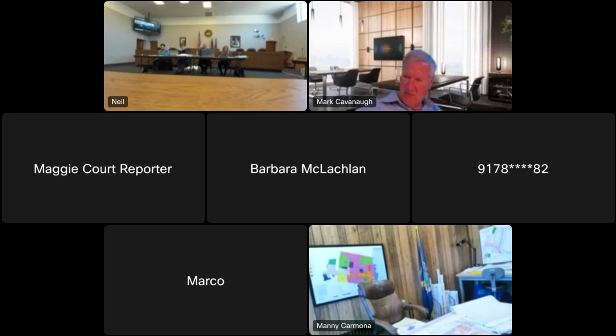So in lieu of that, we're proposing a fire escape in the back of the building, which goes out to grade at that side and provides 2 means of egress for all units, whether by the fire escape and a hallway leading out to the exterior, or fire escape and an emergency egress window opening. The travel distance for 3B construction is 125 feet. We are well below that, with a maximum of 1 unit being 65 feet. We believe without question, the R2 automatically triggers the fire alarm system connected to a central monitoring station. We agree with that, acknowledge it.